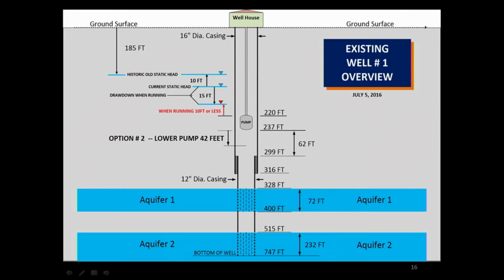And so what they do to clean this well, under the rehabilitation side of it, is they would pull that pump all the way out, and that takes quite a bit of effort. We'd have to demo the well house building so they can clean it. They would pull all the pump out and all the pressure line out and all the electrical wires and everything, so you'd have just a clean shaft. It's kind of like getting your teeth cleaned.